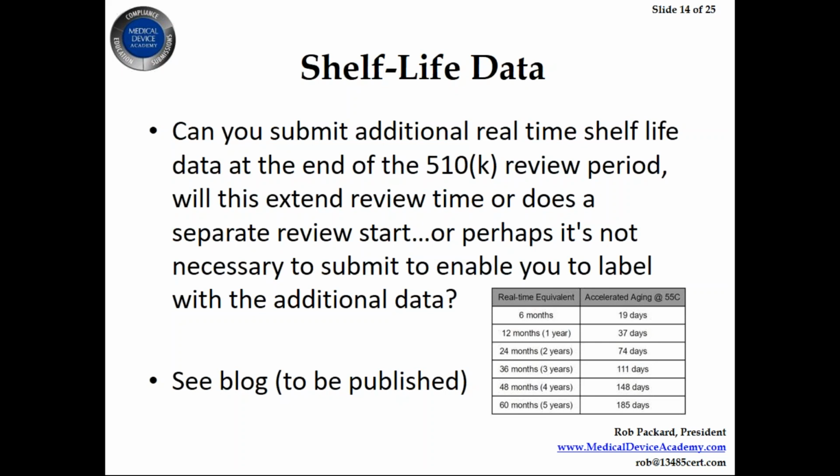And in fact, in the blog that I'm in the process of writing, I give an example of a 510K submission where in the 510K summary, they actually state that they're going to continue to do testing and extend the date beyond 2 years. So they gave an example where we did 2 years of testing data. We're claiming 2 years now, but we fully intend to extend it out to 5 years and do real-time aging for 5 years. But we're not going to do a new 510K to show that data. We're just going to have a letter to file, and we're going to use the same test method and the same acceptance criteria just for a longer period. And the FDA allows that. That's not a problem at all.